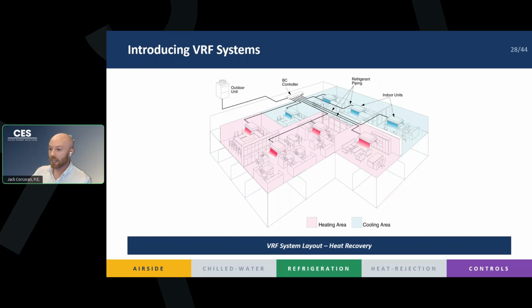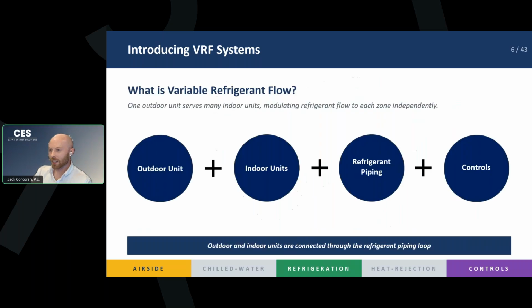So in a heat recovery system, you still have your indoor units, you still have your outdoor unit and your refrigerant piping. The only difference is we have this BC controller, as it says on this diagram, or valve port box or branch selector. There's a bunch of different names for it, but they all act for the same purpose. It just distributes the refrigerant a little bit differently than if you were in a heat pump system. So again, at a high level, we have outdoor units, indoor units, refrigerant piping, and our controls that tie them all together, right? So what is our variable refrigerant flow system? It's all of these components combined, working together in order to move our heat from inside to outside.